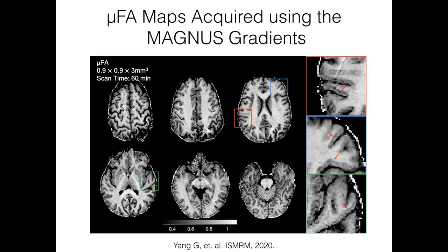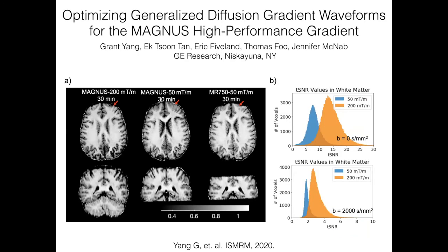People have been very interested in using these techniques to look at gray matter, but not much has been shown so far — partly due to resolution limitations and inability to get intrinsic gray matter signal. With ongoing hardware developments, we'll start to see that. This example shows the SNR boost from the Magnus gradient compared to the 50 mT/m gradients we were limited to on the clinical scanner.